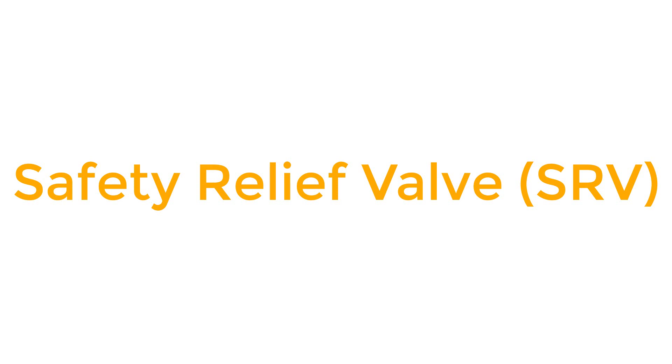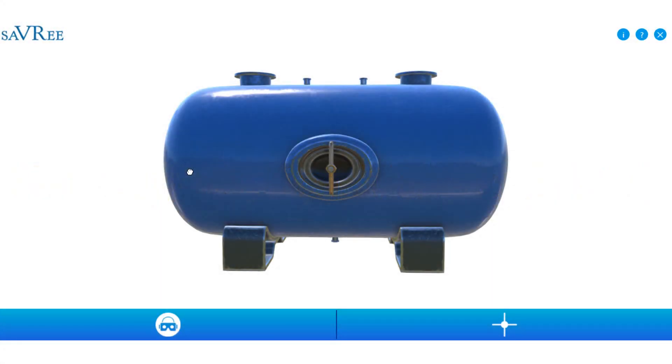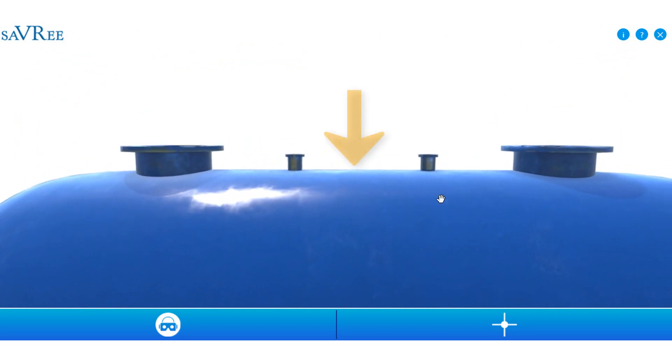So in order to avoid this, we'll have a safety relief valve, one or two of them, and they'll vent in the event that the pressure becomes too large. And we'll also have a fusible plug. Now the fusible plug is normally mounted somewhere near the top, perhaps between these two appendages here, so in the middle.